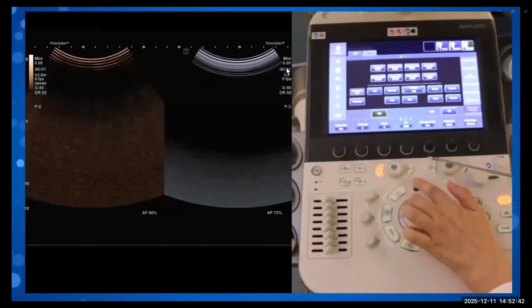How do you adjust these gains? You want to adjust them a little bit high so you see some noise, and then you want to try to pull them back. So you suppress the image on the contrast side before you start your exam. On our console, you want to make sure your TGCs are aligned and straight, and you want to be aware of your focus position. So you want your focus to the back of the image or at the image. And you can see here on the monitor, Canon has two areas of focus, and we have the focus right to the back of the image.